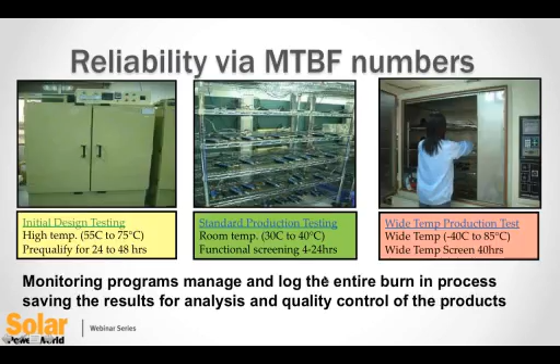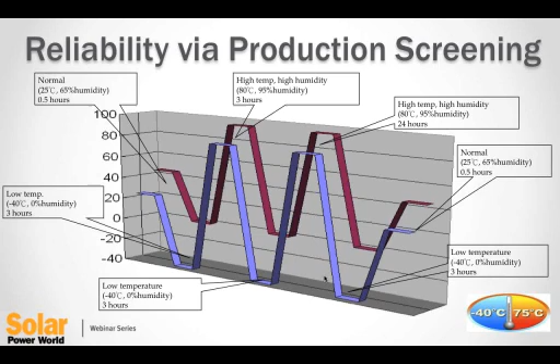We leave it to the R&D engineers to figure that out. But just as a visual example of what happens during production screening, here is an example of a ramp up and down temperature range for a product that we actually ship now, just for you to see. You take it up and down between the temperature and humidity, and once it gets through while functioning—if there's no failures on the software, no errors, the system doesn't crash during the process—it usually gets the rubber stamp and sent out as a proper product.